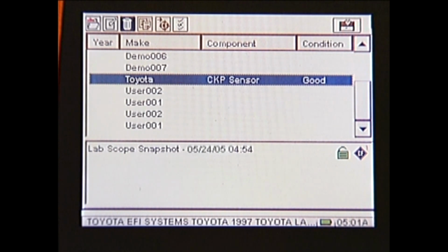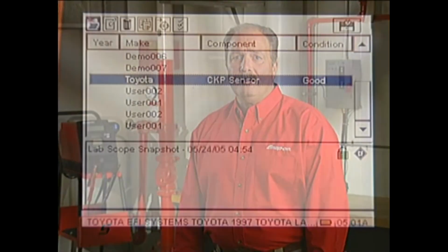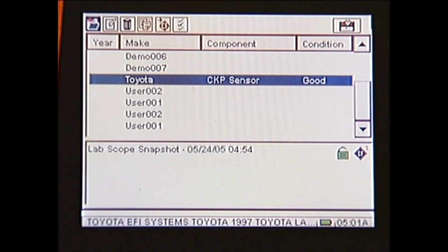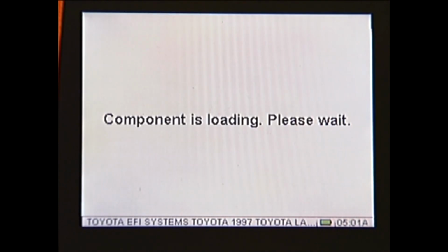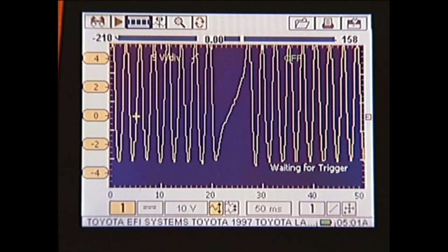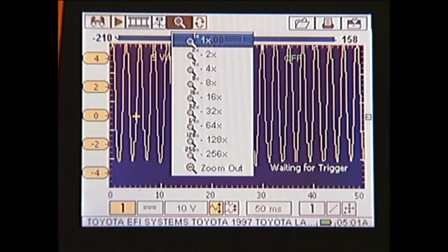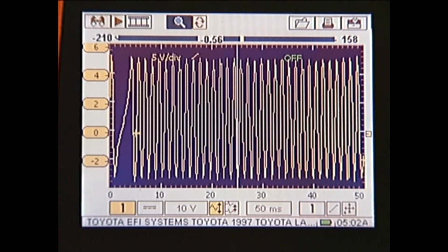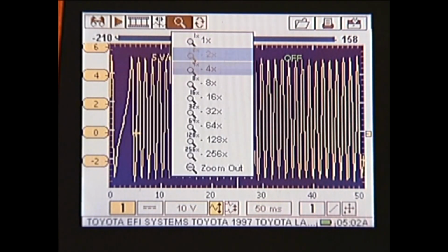It's important to note that you can only see files contained on one compact flash at a time. If a file seems to be missing, it might be saved on the other CF card. We can now open the snapshot we recorded and use the same review and zoom functions to review the captured data. The zoom menu shows a multiplier that is the equivalent of putting that many screens or frames on the display at one time. So, 256X will display 256 continuous screens of data on your Vantage Pro.